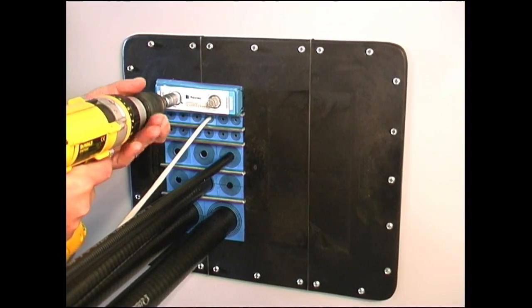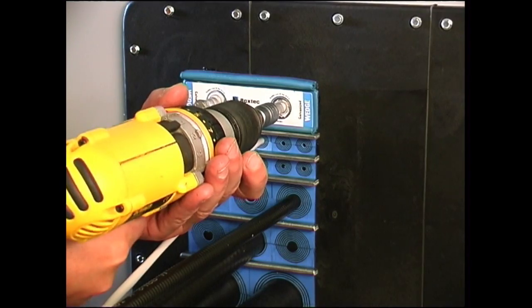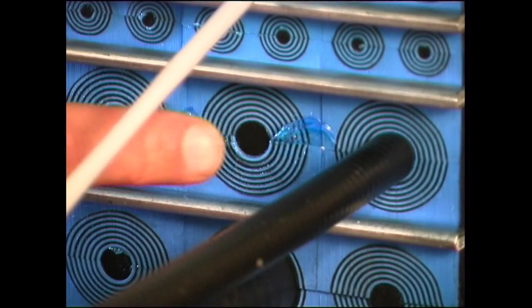Tighten the bolts alternately until stop or to a maximum torque of 20 Nm. The wedge will compress and seal the transit and the excess assembly gel will be squeezed out.